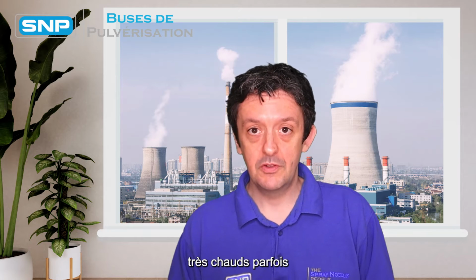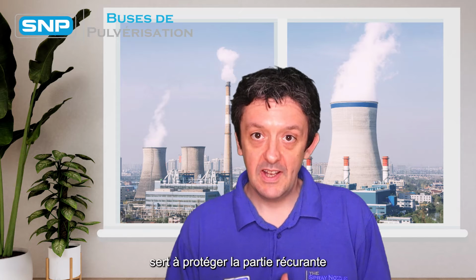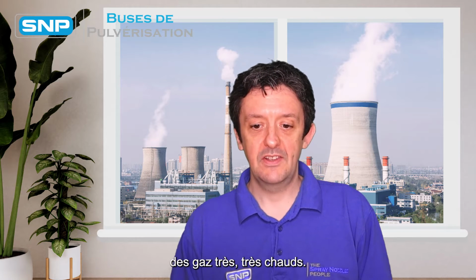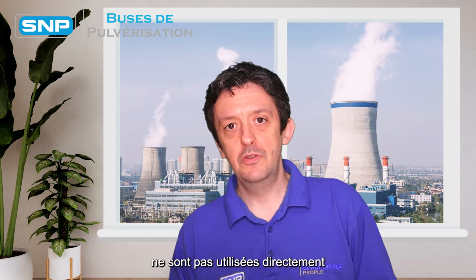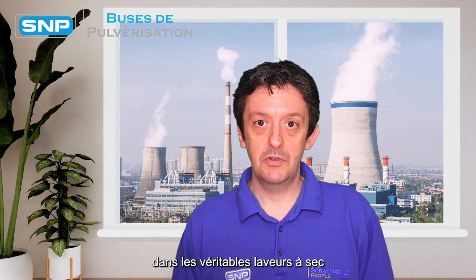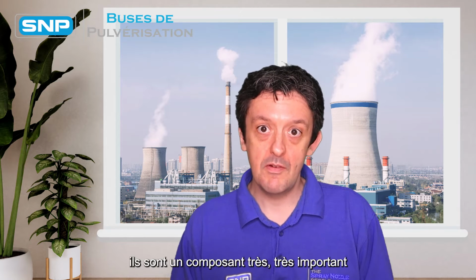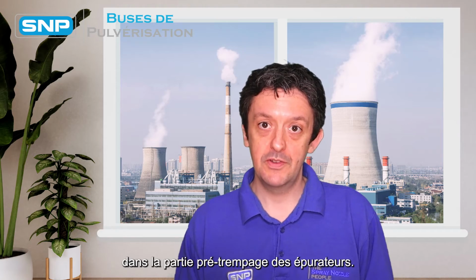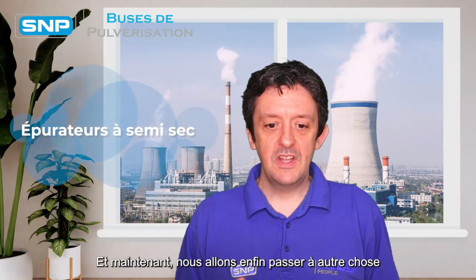And secondly, these gases can be very, very hot sometimes, and so cooling them down serves to protect the scrubbing part of the scrubber from the very, very hot gases. So whilst spray nozzles aren't used directly in true dry scrubbers to actually scrub the gas, they are a very, very important component in the pre-quench part of these scrubbers. So now moving on finally to semi-dry scrubbers.